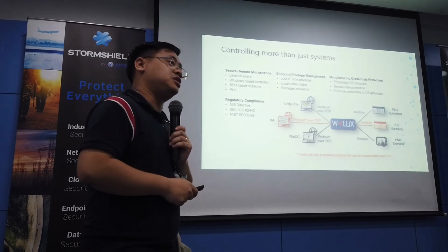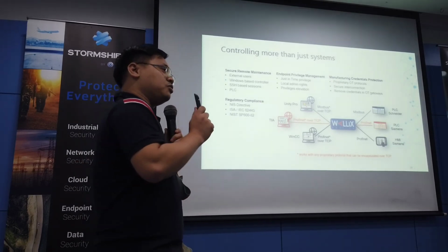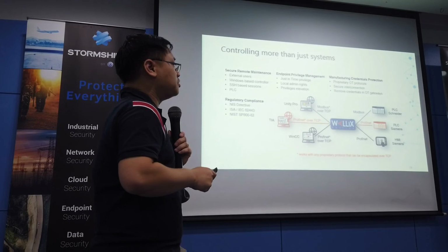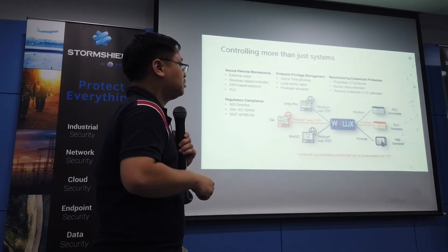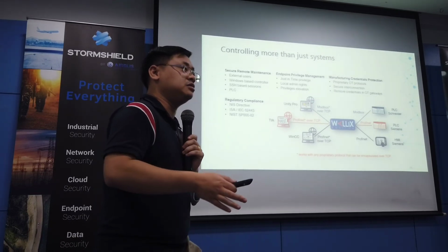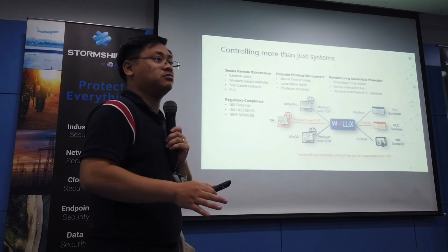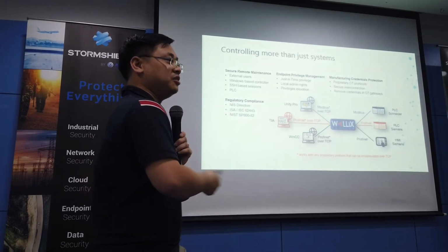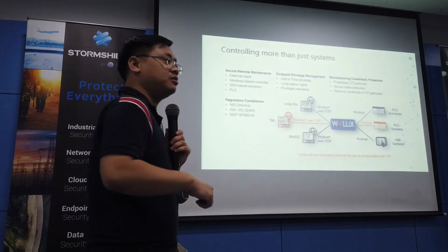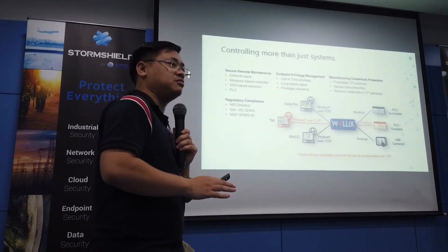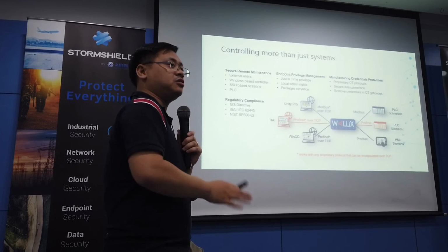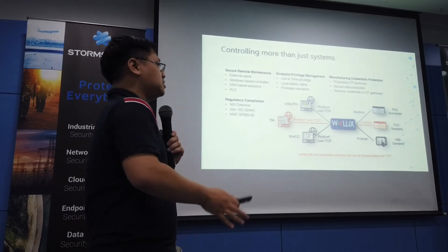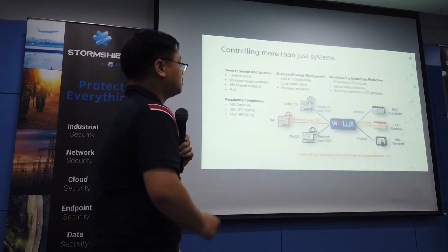You can create a secure connection. Why a secure connection? Remember, Modbus, Profinet, BACnet are not secure by default. If you take Wireshark and scan a network where there's Modbus and so on, nothing is encrypted. It's all in clear. You can see the command, the source, the destination, you can see everything.